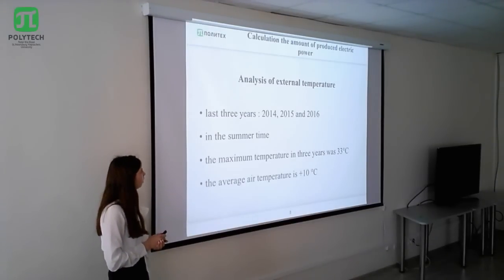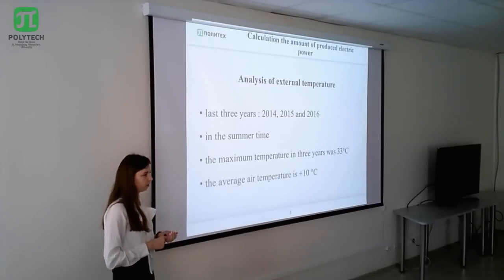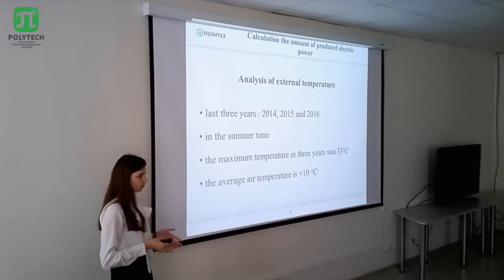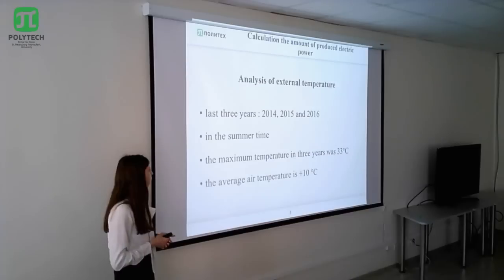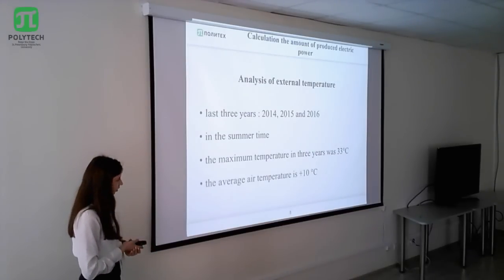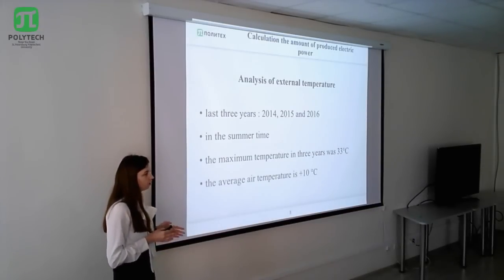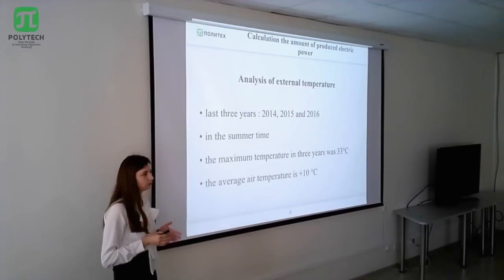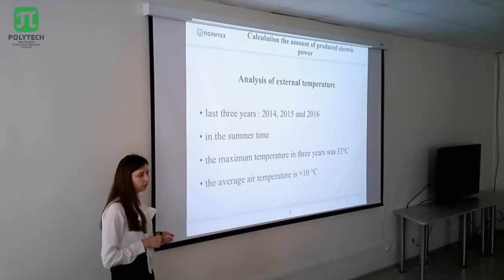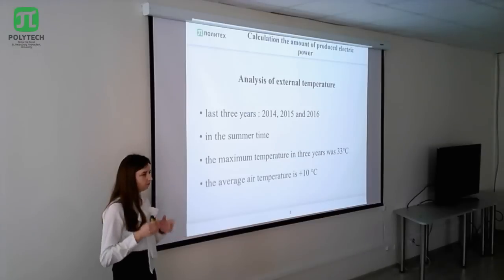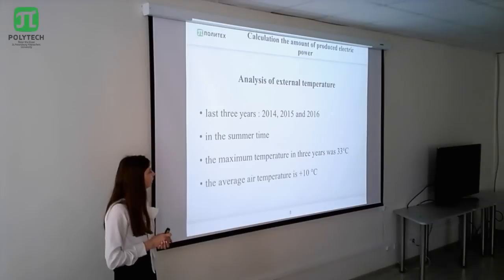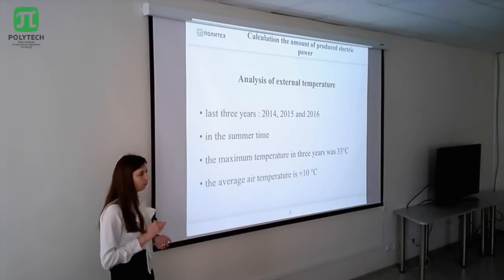The temperature changes were analyzed over the last 3 years, 2014, 15, and 16, in the summertime, from the beginning of May to the end of September, 5 months. The maximum temperature in the year was 33 degrees Celsius. The nominal external air temperature for operation of the gas turbine is 10 degrees. At an ambient temperature from +5 to -5 degrees Celsius, the anti-icing system is activated. I take the average temperature between 15 and 5 degrees, and take +10 degrees Celsius for further calculation.